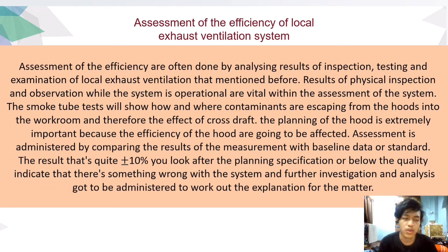Assalamualaikum warahmatullahi wabarakatuh. I'm Muhammad Kual Hafiz bin Waizi. Now I'm going to present about assessment of efficiency of local exhaust ventilation. Assessment of the efficiency is often done by analyzing the results of inspection, testing and examination of local exhaust ventilation mentioned before. Results of physical inspection and observation while the system is operational are vital within the assessment of the system.